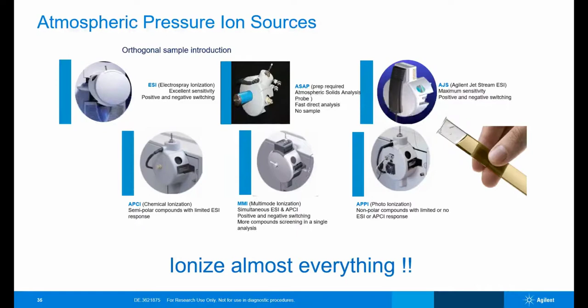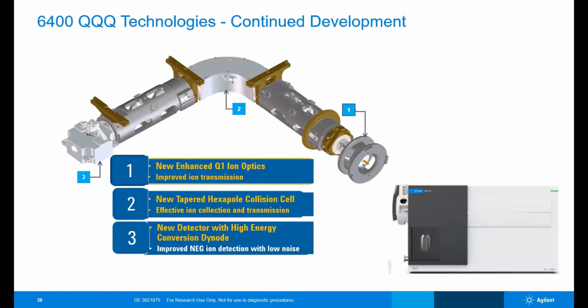And here is the design for 6470 LC triple quad, which is a curved design to reduce its footprint a little bit. And then it includes new enhanced Q1 ion optics, which helps in improving the ion transmission, new tapered hexapole collision cell, which again helps in effective ion collection and transmission, and new detector with high energy conversion dynode, which especially is important in case of improvement of negative ion detections with low noise.